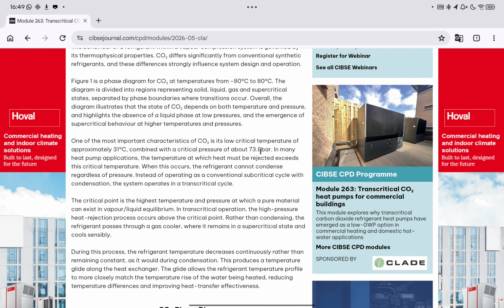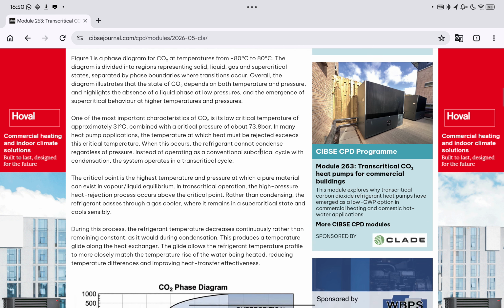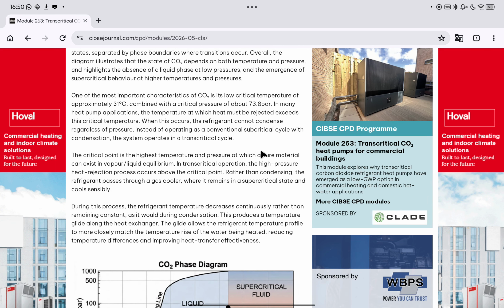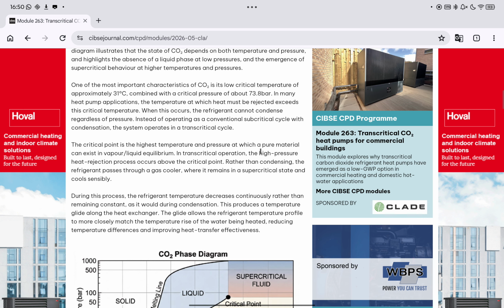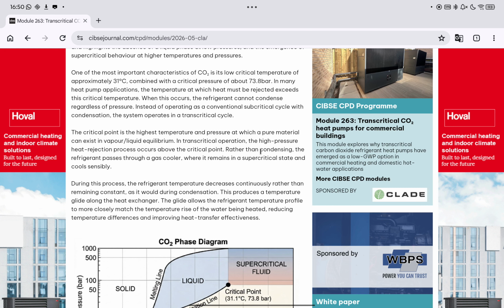Rather than condensing, the refrigerant passes through a gas cooler, where it remains in a supercritical state and cools sensibly. During this process, the refrigerant temperature decreases continuously rather than remaining constant as it would during condensation. This produces a temperature glide along the heat exchanger. The glide allows the refrigerant temperature profile to more closely match the temperature rise of the water being heated, reducing temperature differences and improving heat transfer effectiveness.